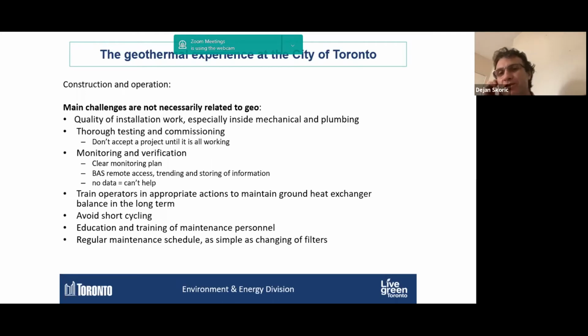I mentioned short cycling. It really starts at the design stage - you have to put in buffer tanks, for example. But from the operator's point of view, they need to know what short cycling is and what they can do to stop it. Otherwise, heat pumps, like any other mechanical system, can run into problems and burn out over time. It also comes down to basic maintenance, which could be as simple as changing filters - that makes a big difference.